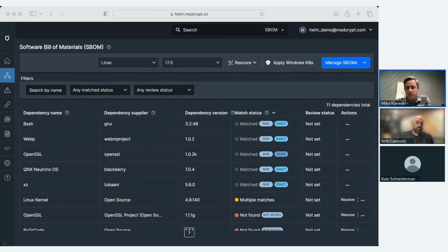We've seen situations where we get an SBOM from a customer and we get an analysis of that SBOM that they have done, and we find that they found 100 vulnerabilities, we found 80. And after we look into it, it turns out that out of the 100 the customer found, 50 of them are just very clearly false positives, right? They relate to software that is just objectively not in the SBOM. And then of the 80 that we found, maybe we find 15 or 16 that the device manufacturer didn't, and 2 of them are of critical severity.